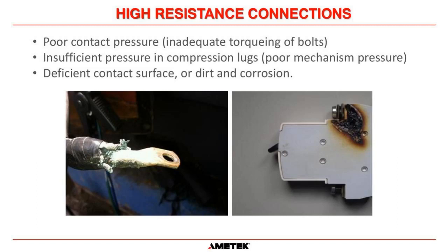Okay, and they can be caused by poor contact pressure. In other words, inadequate torquing of the bolts. So when you land a cable, you don't torque down the bolt properly and you have a loose connection. It could be insufficient pressure in the compression lug. In other words, the lug wasn't made correctly. And you can see on the left picture there that lug, I don't care what anybody says, has not been made correctly. You can see that some of the strands of the cable have been cut. And if I had to guess, that lug is not the correct size for that cable, and they've had to try and trim some of the strands so it can fit inside that lug. So poor mechanism pressure can cause high resistance connections.